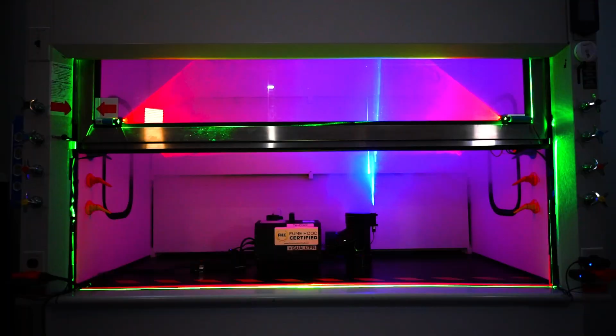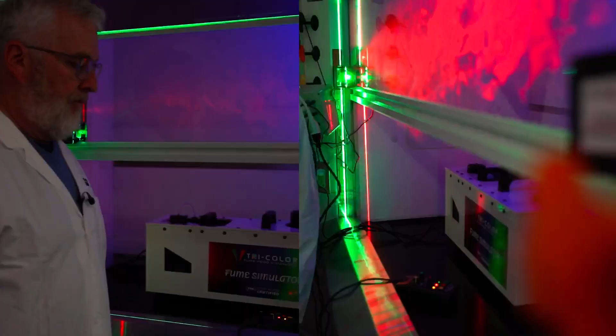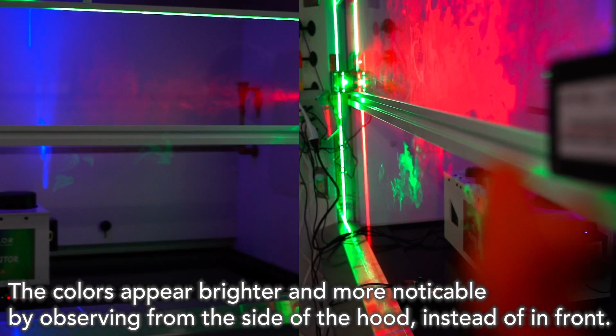With the walk-by challenge, you can almost always get at least some loss of containment, even from a hood that's performing really well. To perform the test, you want to have somebody walk right in front of the hood at a brisk pace, maybe at a slow pace, go to the left, go to the right, just walking by and causing turbulence in different ways to challenge that hood to see if it can keep the fumes in its chamber. Sometimes you can get a better view of the smoke and how it behaves if you stand slightly to the side of the hood as opposed to right in front of it.